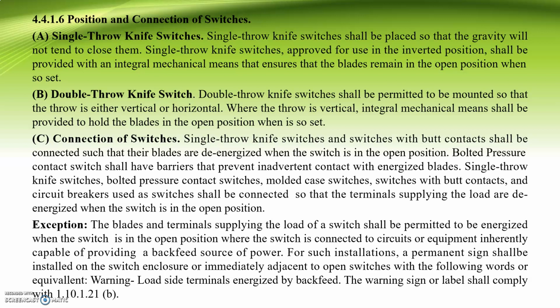Chapter 4.4.1.6, position and connection of switches. A, single throw knife switches. Single throw knife switches shall be placed so that gravity will not tend to close them. Single throw knife switches approved for use in the inverted position shall be provided with an integral mechanical means that ensures that the blades remain in the open position when so set.